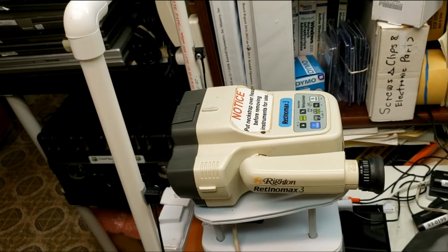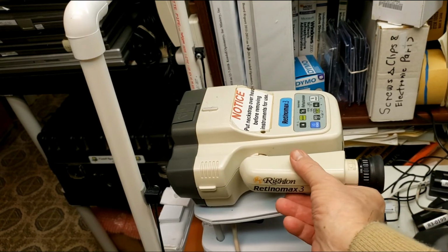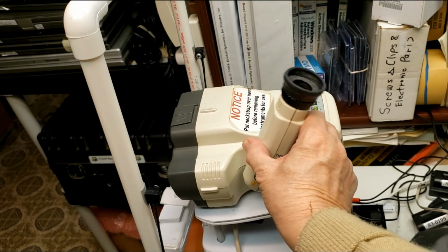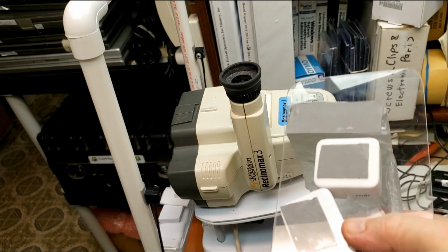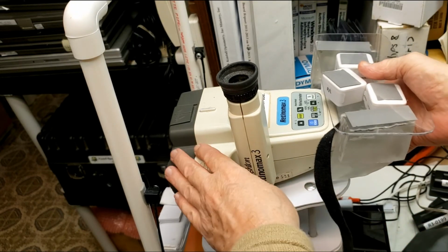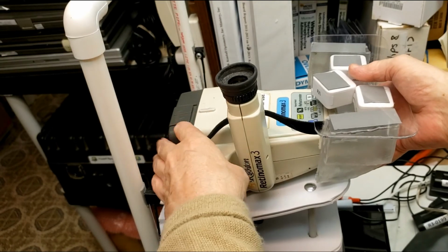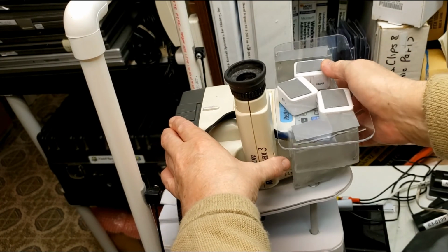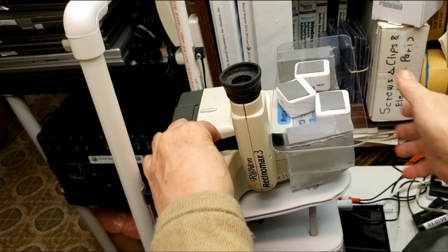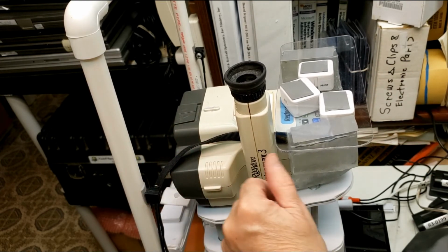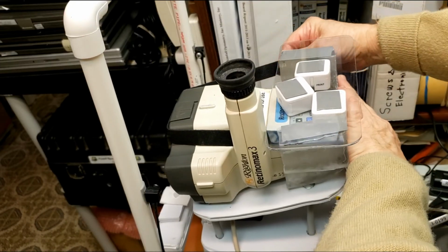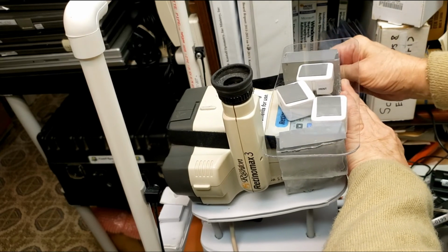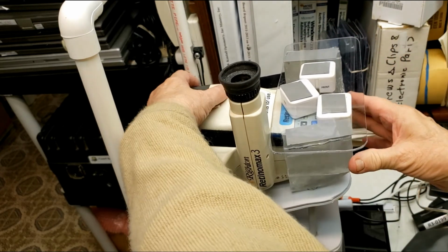Okay, now what you need to do is make sure this headrest, this little eyepiece I should say, is up vertical. Then you take this and orient it like this and place it on the back of the autorefractor. You want to thread this between the eyepiece and the autorefractor back. And then you want to thread this around in front of the instrument, push hard on it, and put it down on the Velcro on the other side. This piece of Velcro is what holds it in place.